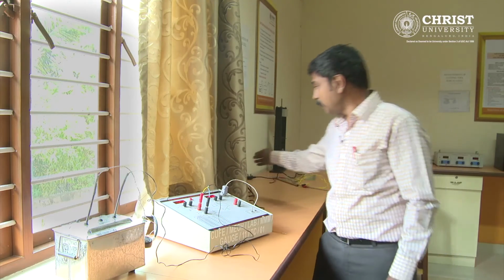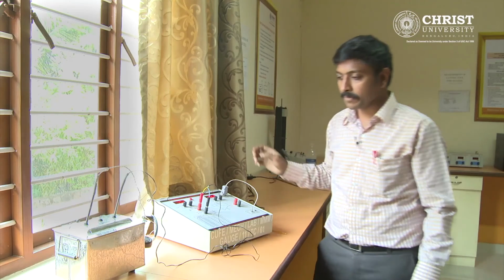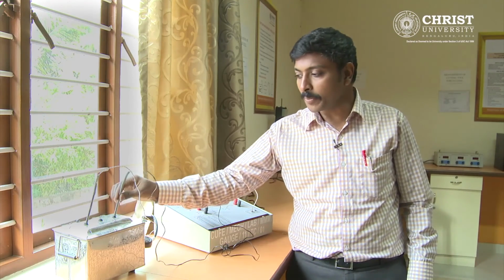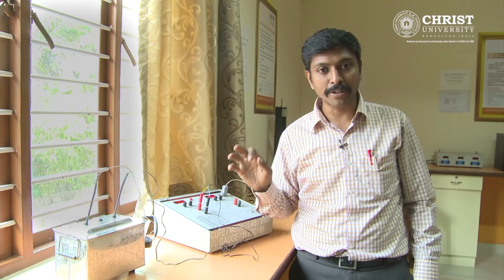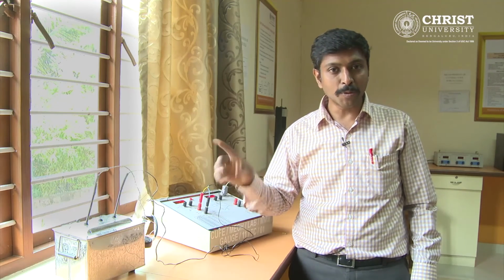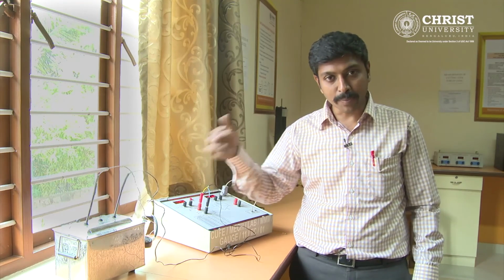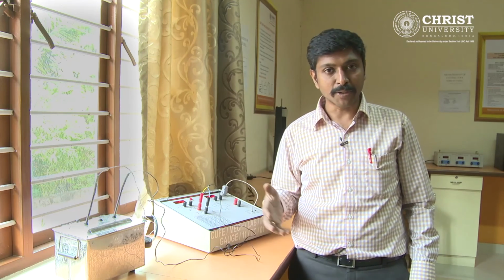Now what we have to do after you finish is replace the J-type thermocouple with the K-type thermocouple. There are 3 thermocouples provided to you, and you have to replace it with the K-type thermocouple. How do you know which is the K-type thermocouple? You will be provided with a yellow color wire. You have to take the black color one outside, replace the water with cold water, insert the yellow wire inside and repeat the same procedure. You will get the values for that also.